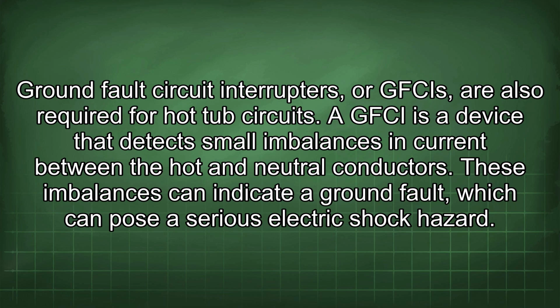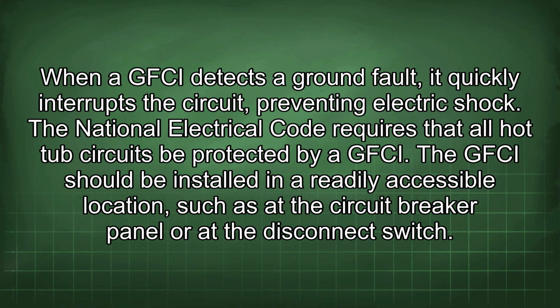Ground fault circuit interrupters, or GFCIs, are also required for hot tub circuits. A GFCI is a device that detects small imbalances in current between the hot and neutral conductors. These imbalances can indicate a ground fault, which can pose a serious electric shock hazard. When a GFCI detects a ground fault, it quickly interrupts the circuit, preventing electric shock. The National Electrical Code requires that all hot tub circuits be protected by a GFCI.